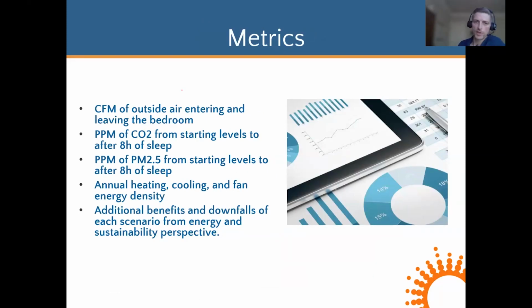And the metrics we were looking to study: the CFM of outside air moving in and out of the bedroom, CO2 parts per million from starting, which is equal to outdoor levels, to after 8 hours of sleep, PM 2.5 levels from starting to after 8 hours of sleep, and then the heating and cooling fan energy, and any additional benefits and downfalls of each scenario we wanted to include in the analysis.